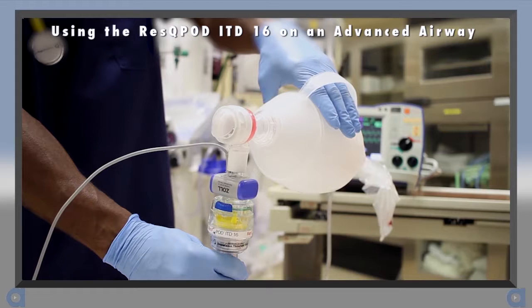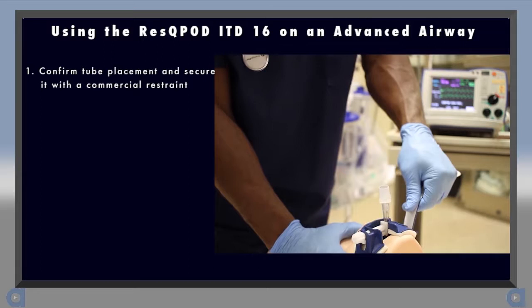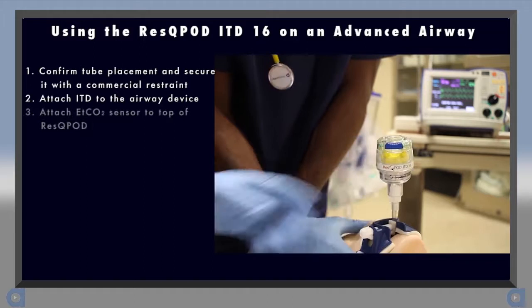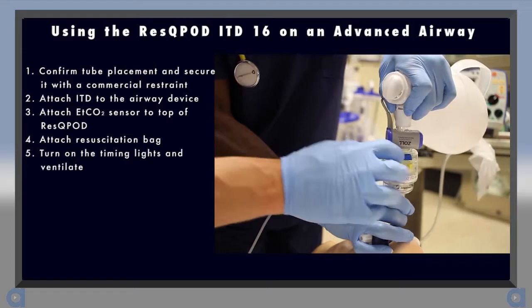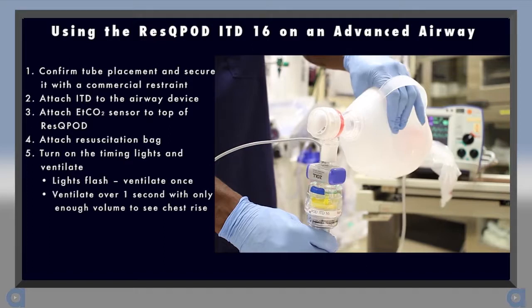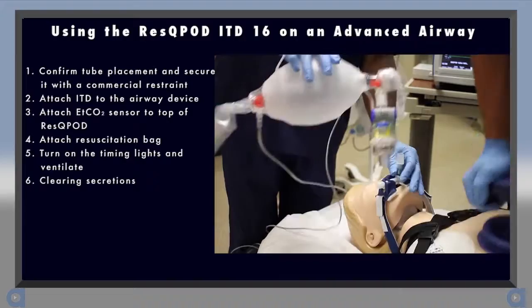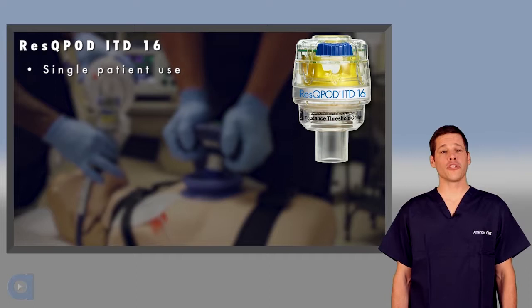Now, let's discuss how to use the ResQPOD ITD-16 on an advanced airway, such as an ET tube or supraglottic airway device. Once an advanced airway has been placed, secure it using a commercial tube restraint. Then, attach the ResQPOD to the airway device. Next, apply an end-tidal CO2 sensor if available. After that, attach the resuscitation bag. Now, turn on the timing assist lights, which flash 10 times per minute. Each time the lights flash, provide one ventilation. Remember, ventilate over one second and with only enough tidal volume to achieve chest rise. If the ResQPOD fills with secretions, remove it from the circuit and use the ventilation source to clear it. The ResQPOD ITD is for single patient use only and should be disposed of properly after use.